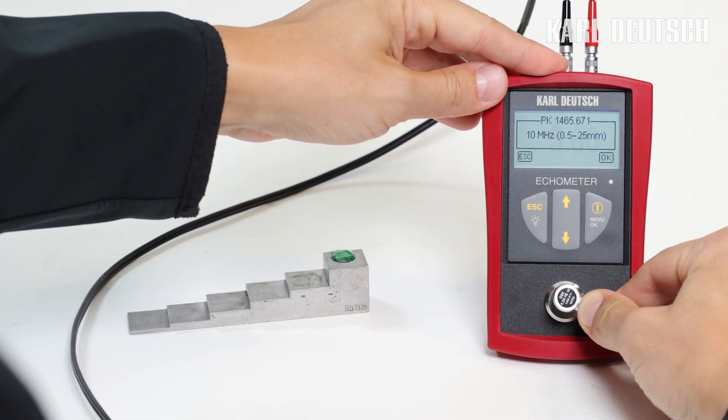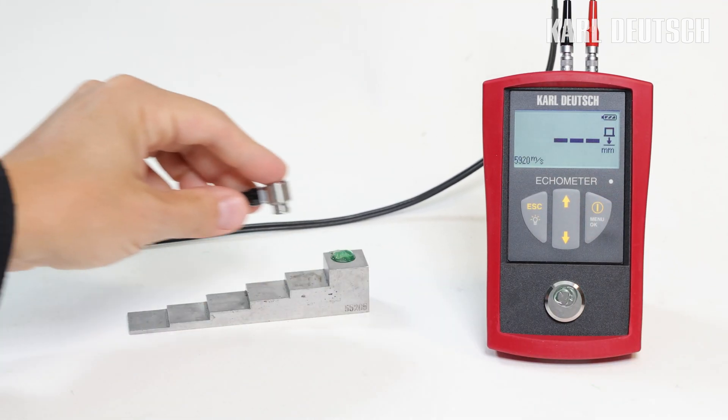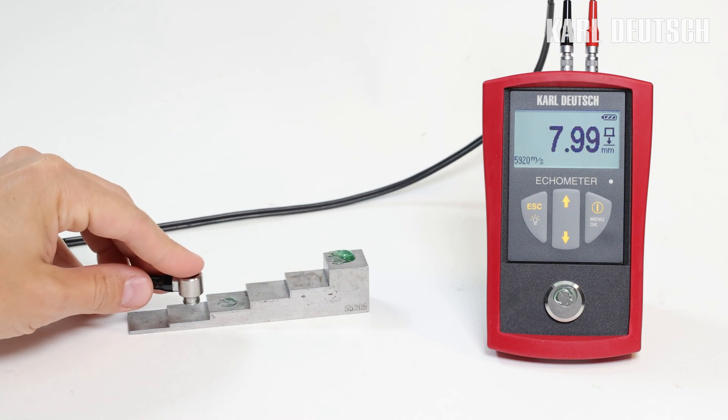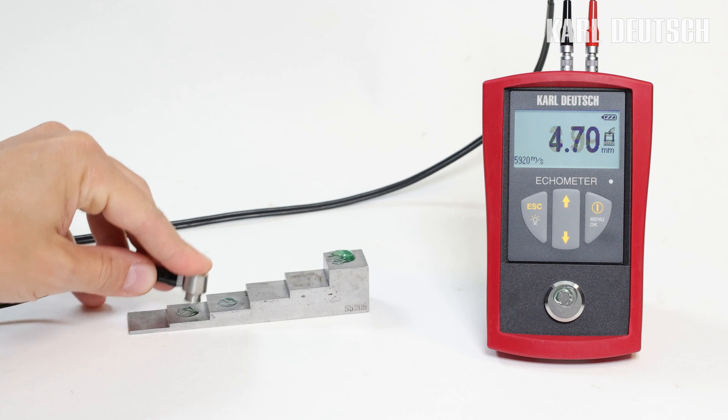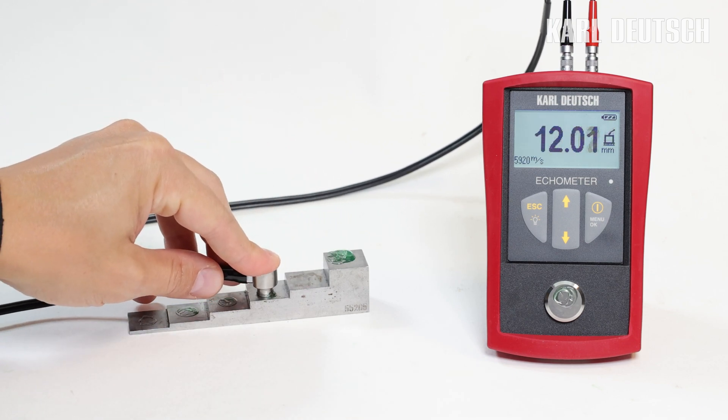The instrument is then ready for measurement on steel. For the measurement, the probe is placed on the measuring point and the gauge shows the wall thickness on the display with an accuracy of 0.01 mm. The measuring accuracy is approximately 0.1 mm.